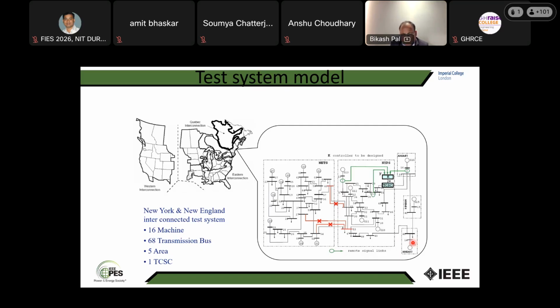Why? If you have 2 masses and 1 spring, you have 1 frequency of oscillation. So 2 areas connected by 1 line. If we have 3 areas, so area 1 to area 2, and then area 1 to area 3, there will be 2 modes. And that means if there are n number of areas, there will be n minus 1 number of modes. This is a 5 area system, there will be 4 modes.